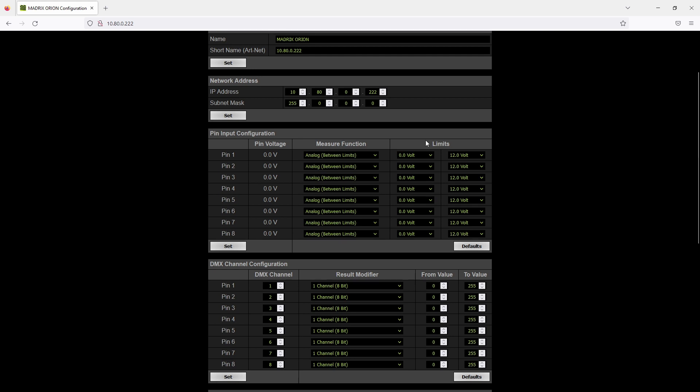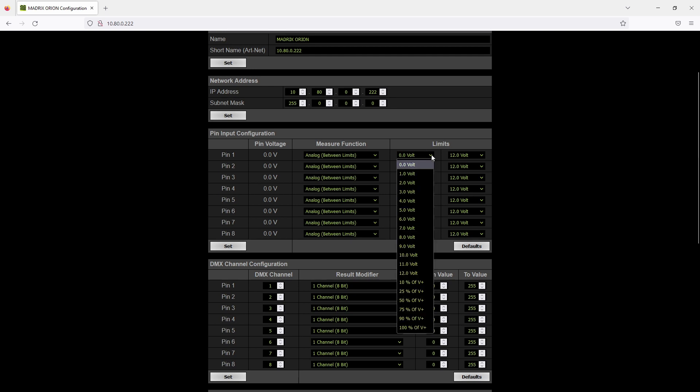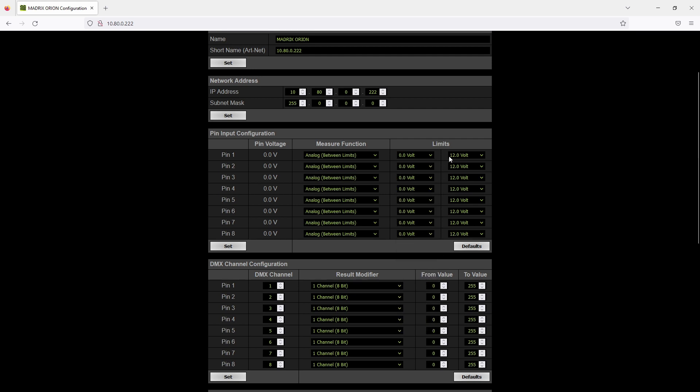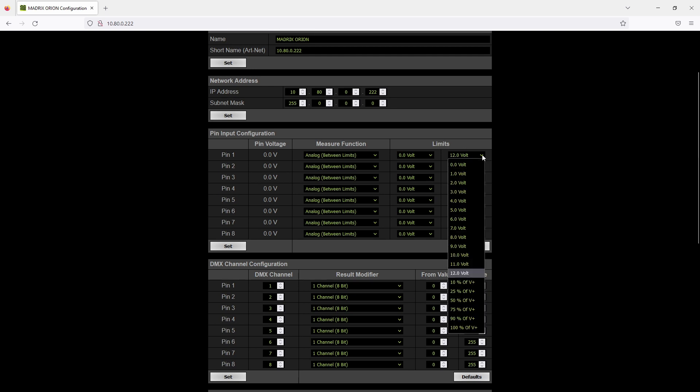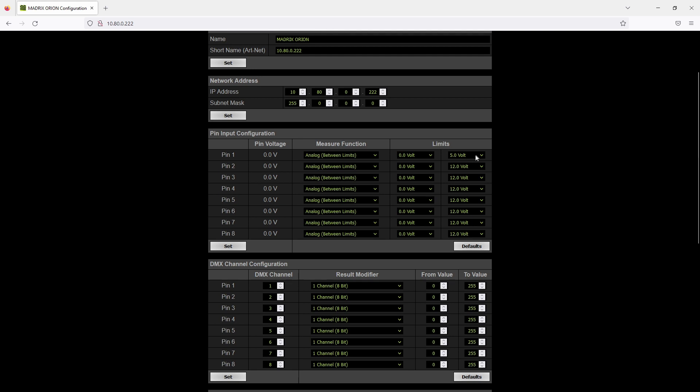In the section right beside the measure function you can define in which range the analog input signal is received. 0 is the lowest, so for the minimum value you can change this in 1V steps between 0 and 12V or in percent steps. And also for the maximum you can give the maximum value that should be measured. This is important when you are using it as analog or digital input and you don't want to measure between 0 and 12V. Maybe you have connected only a 5V power supply so you can limit it to 5V and that means 5V is your maximum now. After changing any settings please click set in the desired section.